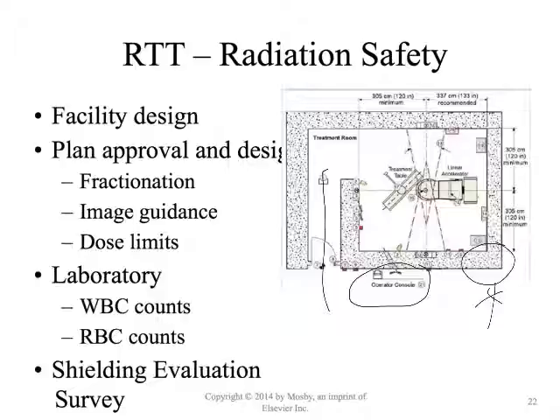And then in addition to that, every morning the radiation treatment machine goes through a warm-up procedure and quality check as well as interlock checks. And so we make sure that, for example, the machine can't be operated when the door is open, or the machine cannot be operated if it's not aligned properly. There's all these different interlocks that have to be satisfied before we can turn that machine on.